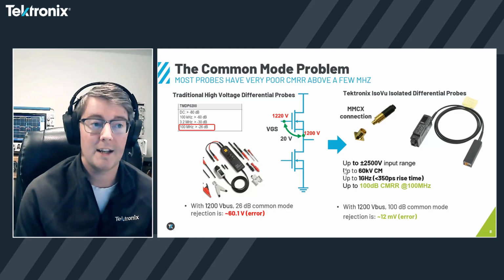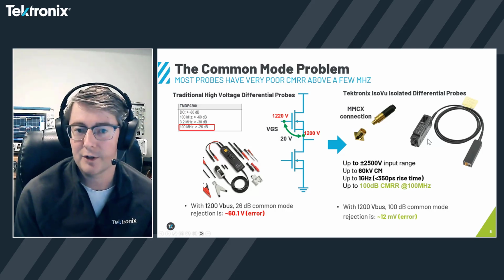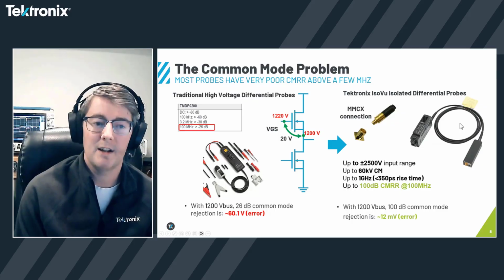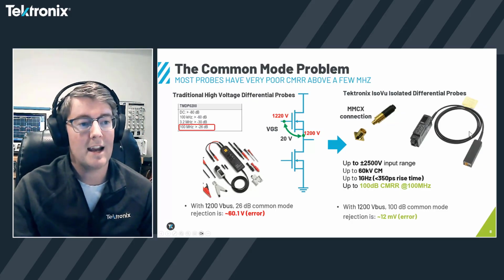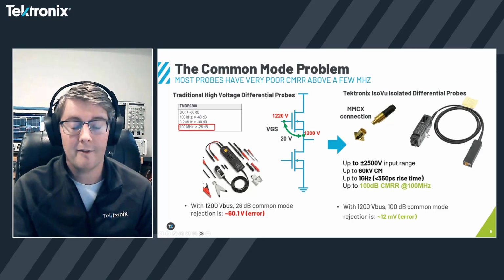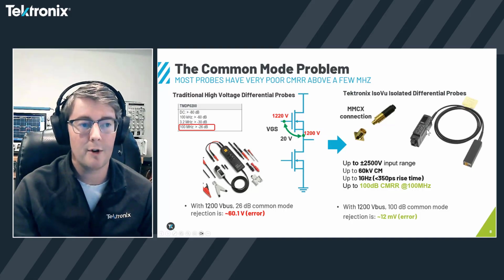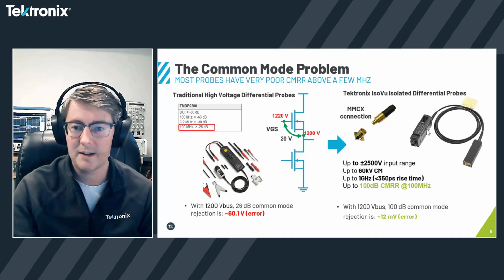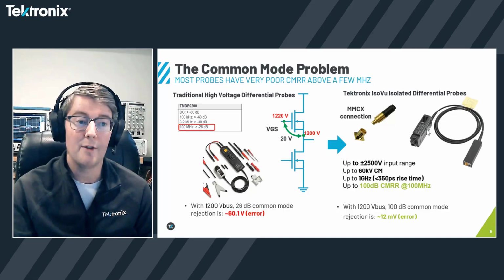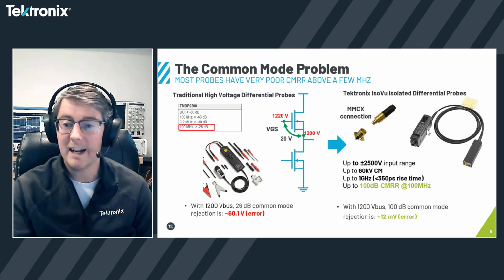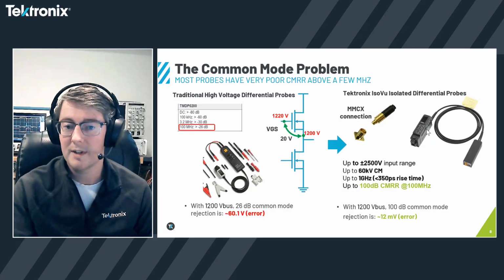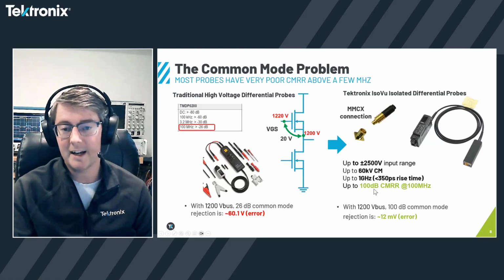Our solution to that is using what's called an isolated differential probe. In this case, our probe has 5 fiber optic cables that go between the probe head and the compensation box back on the scope connection. Those fiber optic cables galvanically isolate the probe head from the scope.